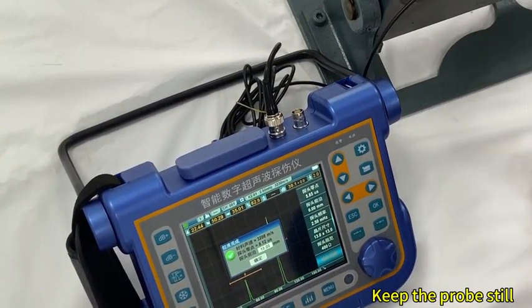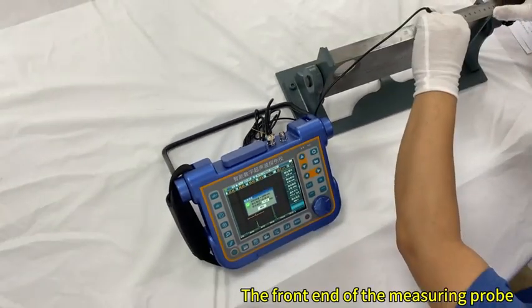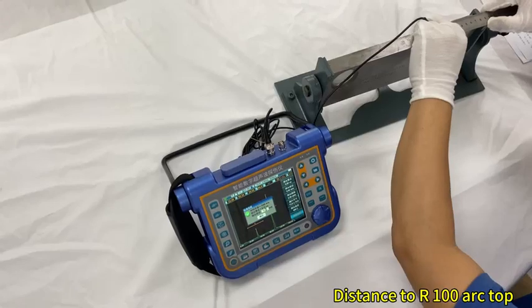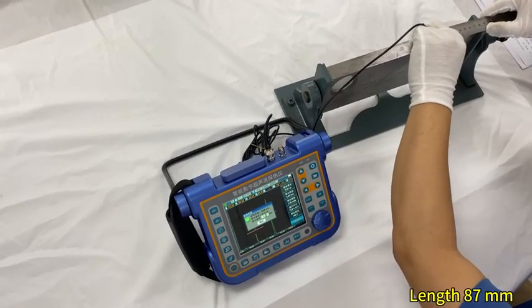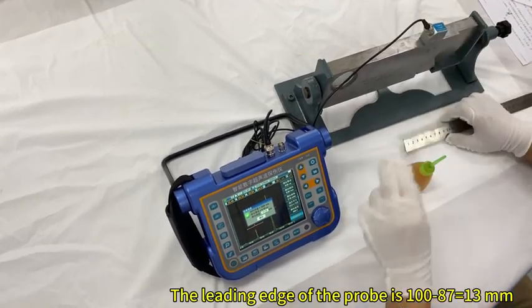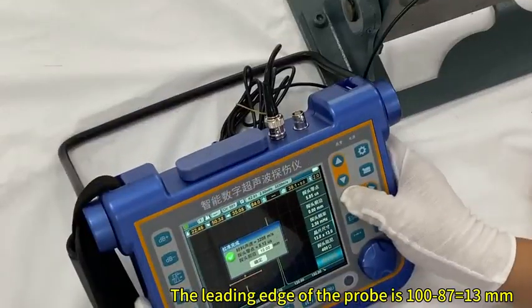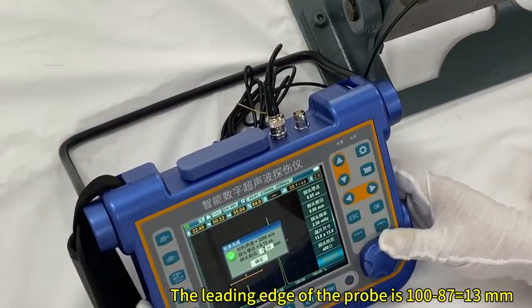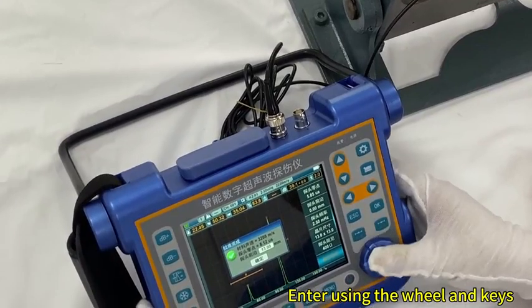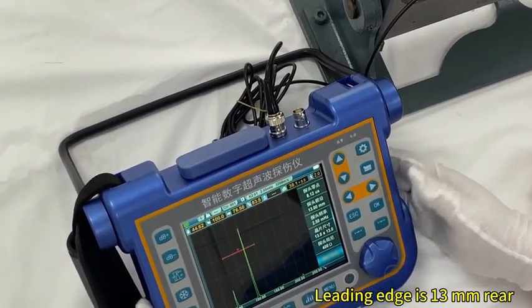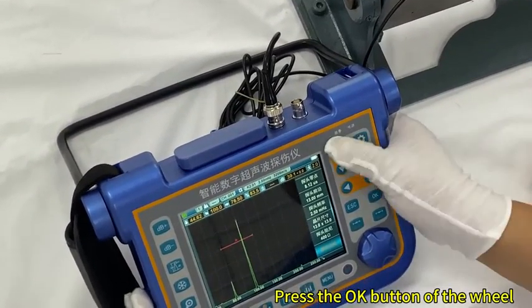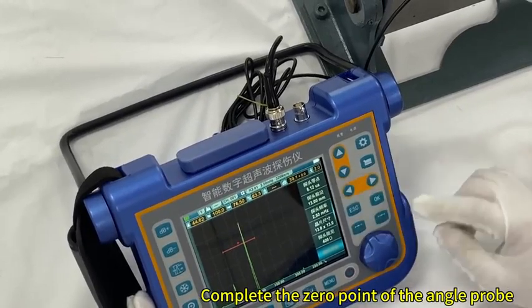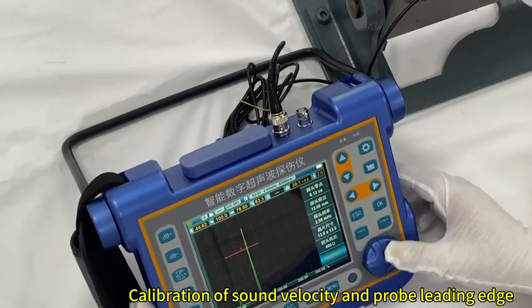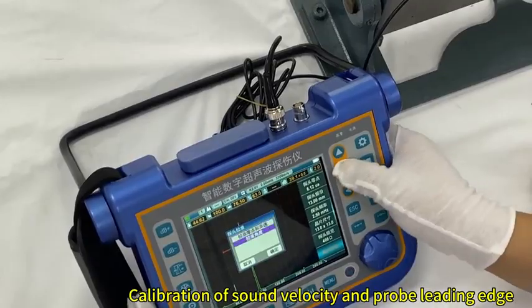Keep the probe still. Use a steel ruler to measure the distance from the front end of the probe to the R100 arc top. Length 87 mm. The leading edge of the probe is 100 minus 87, which is 13 mm. Enter it using the wheel and keys. Leading edge is 13 mm. Press the OK button of the wheel. This completes the 0 point of the angle probe, and the calibration of sound velocity and probe leading edge.